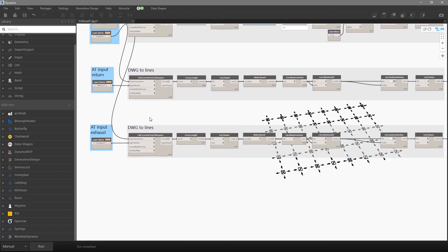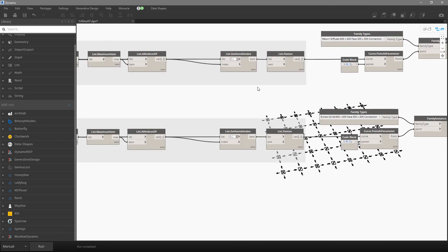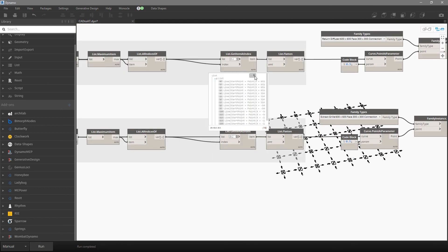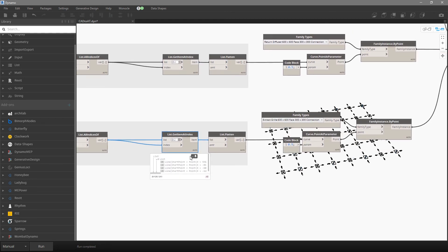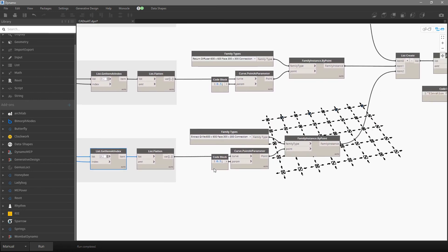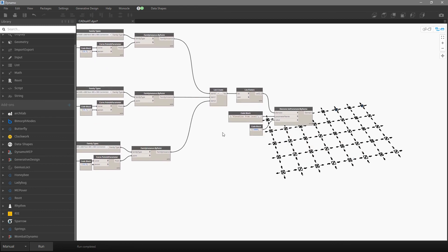It is a very similar story for exhaust and return: get the lines, find the line length, flatten, round, find the maximum element, find the number of those elements, get the indexes, and take those lines. For return we have 16 diffusers, for exhaust only four. We flatten both lists, find middle points, and assign the appropriate family — this family for return diffuser, this family for exhaust.